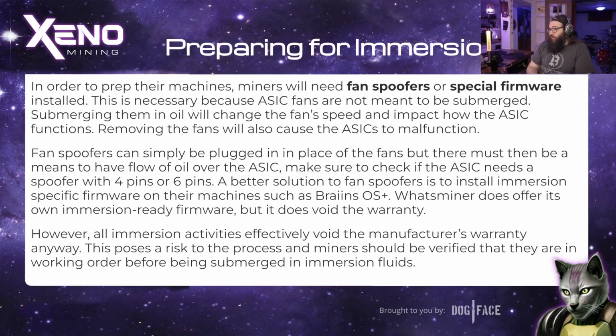This is necessary because ASIC fans are not meant to be submerged. Submerging them in oil will change the fan speed and impact how the ASIC functions. ASIC fans are meant to churn through air—they're literally chopping up air. The moment you put a fluid through them, now there's a form of resistance, so the fan has to work overtime to make it through.